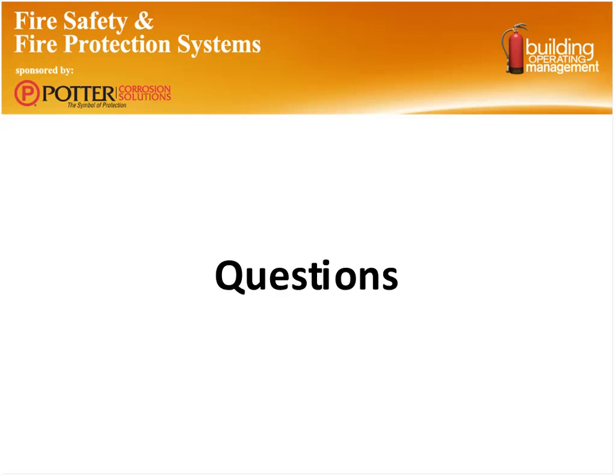To find out if a fire door is required, you really want to refer back to NFPA 80, and it has to do with the fire-resistive construction of any particular area. So if you look at the International Building Code and the International Fire Code, which ultimately reference back to the NFPA requirements, in this case fire doors NFPA 80, you will find some of the fire-resistive construction and requirements for where those doors should be. Okay, great, thanks.